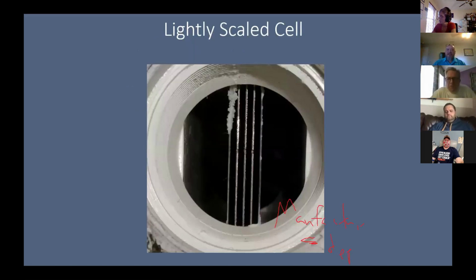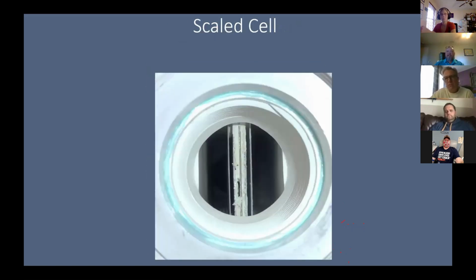This is what it looks like inside of a cell when a cell gets scaled up. This is easily cleaned off by the self-cleaning feature. When it reverses polarity, it'll clean that scale back off. When you start getting into a position like this, where it's bridging between the cells, that's where a cell is being neglected. Goes back to, is it saturation index that's allowing that scale to build up, or is the unit reversing polarity correctly?